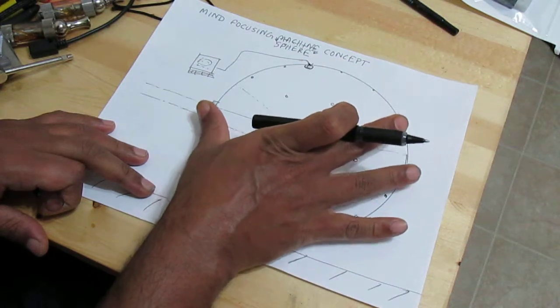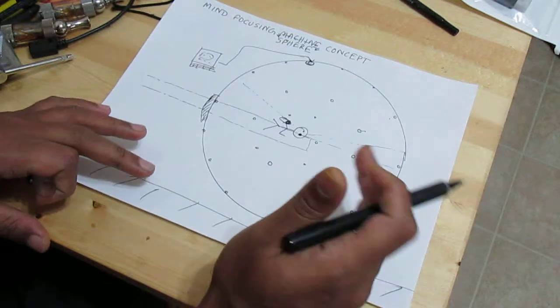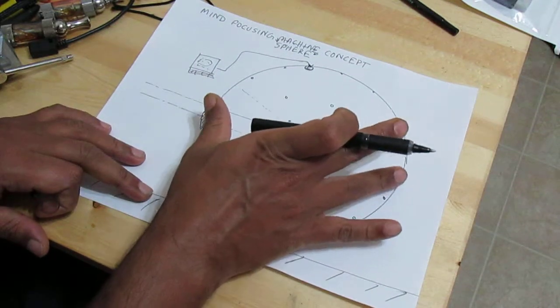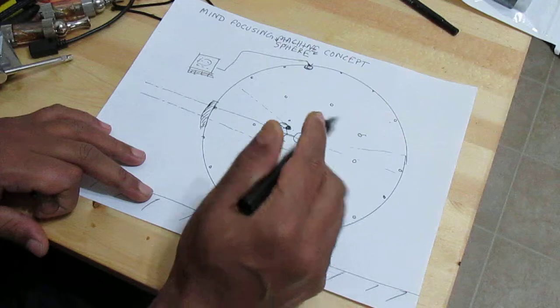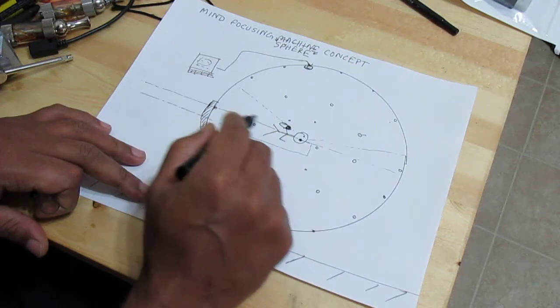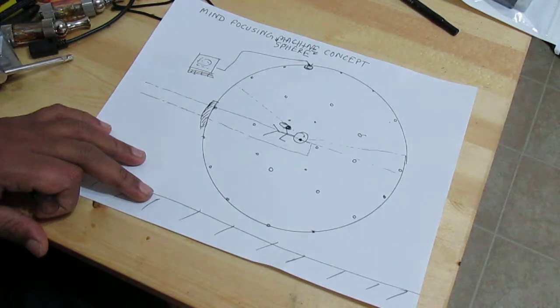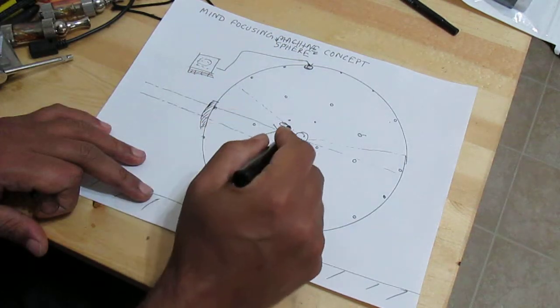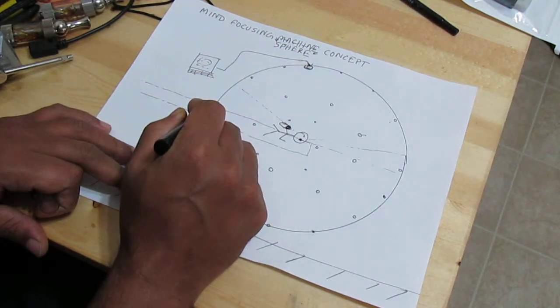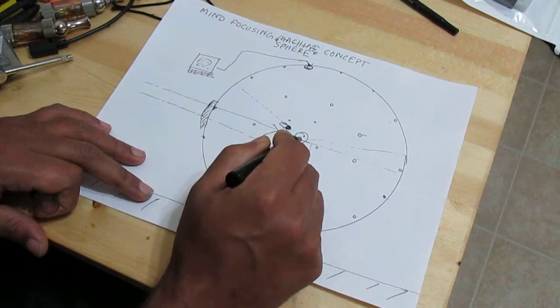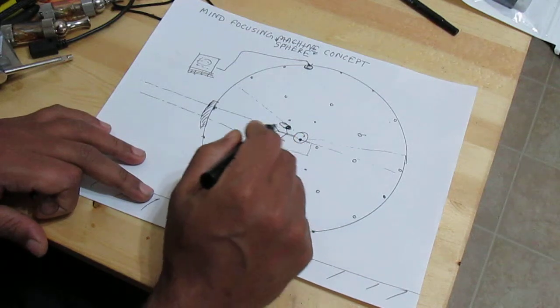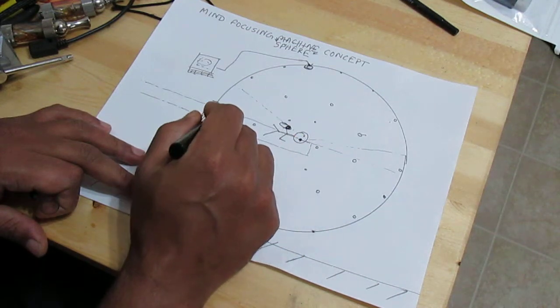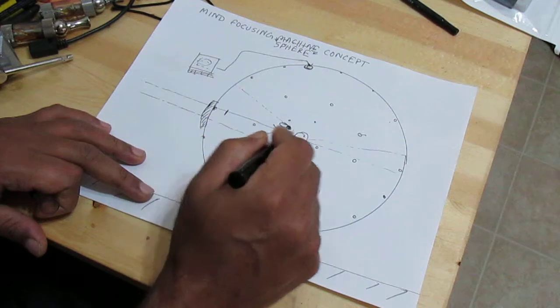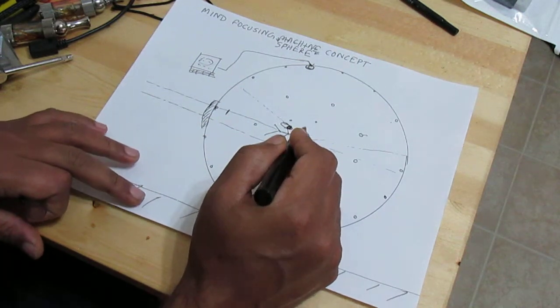The size of the sphere, my guess, is about 14 feet in diameter, because the average human length is about 6 feet. So we want the distance from the side to the center to be about 7 feet, because then a patient's legs, at 6 feet, will come up to here, and the head will be here.